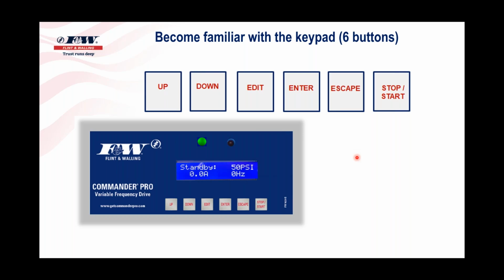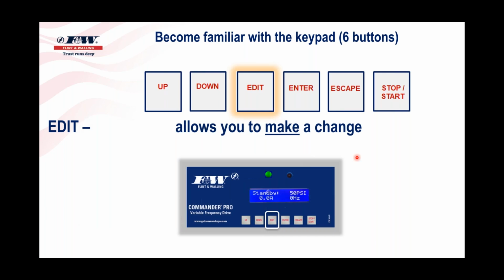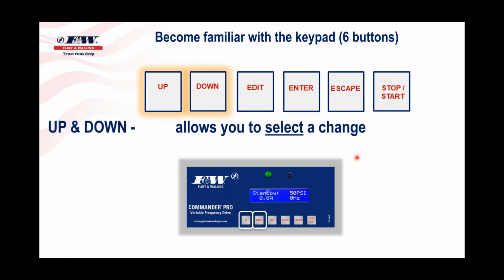So if you ever want to make a change in the drive programming, you want to change the factory setting of 50 psi, you want to run it up to 60 or 65, one of those 6 buttons is going to allow you to make a change. And I think most of you, if you look at those buttons, it's obviously the edit. The edit button will allow you to make a change. And so just for example, if you want to change that pressure setting from a 50 psi set point up to 60 or 65, you would hit edit, and it's going to ask you to make your change. And then you're going to use your up and down buttons, and you're going to scroll up or down to achieve, in this case, we're going to run it probably up to 60 or 65 psi. If it happens to be frequency, it's the same thing. You're moving the frequency up and down or anything else. It's going to allow you to select what change you want to make, those up and down buttons.